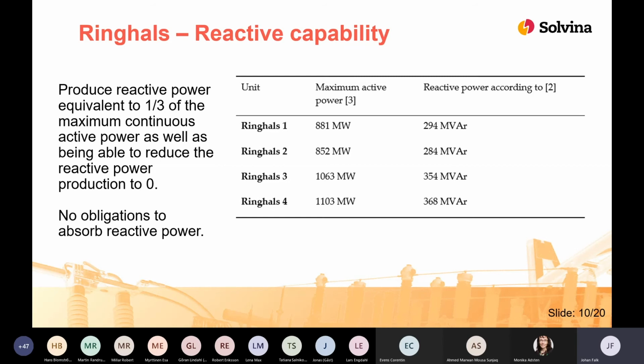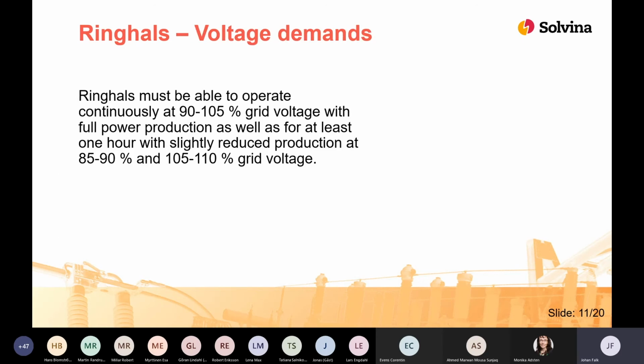And the grid code states that a unit should be able to produce 1/3 of the active power as reactive power. And there are no formal demands or obligations for the units to be able to absorb reactive power. It only states production. According to the grid code, Ringhals must be able to operate continuously at 90 to 105% grid voltage. And if the voltage is slightly outside this range, so 85 to 90, 105 to 110, it should be able to operate for 1 hour with a slightly reduced power production. I think slightly reduced means that it can be up to 10% reduction.